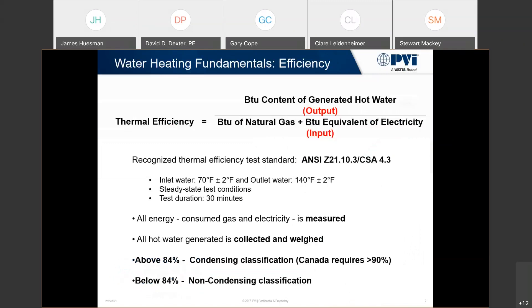This is basically ANSI Z21.10.3's efficiency calculation. It's pretty simple. They're taking the amount of BTUs generated to create hot water and dividing that by the amount of BTUs of natural gas and any electricity or other inputs that go into making that hot water, and that gives you your thermal efficiency.